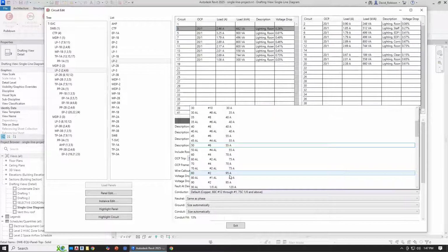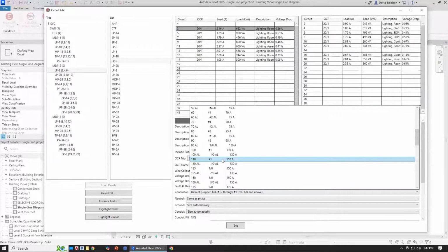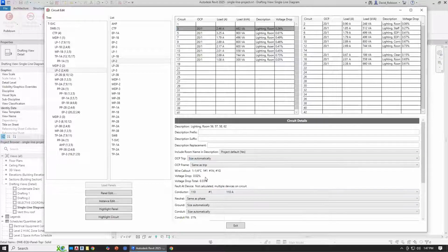something large, if we take this up to 100 amp wire, if you needed that for whatever purpose, you're going to get a number 1 conductor and also a number 1 ground, because it's going to upsize proportionally. They were the same size, so they're going to continue to be the same size. So whatever size wire you choose, you're going to end up with the same size ground. So that comes up a little bit when people are upsizing their branch circuits.